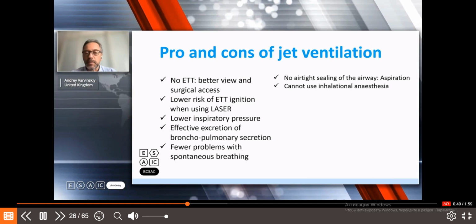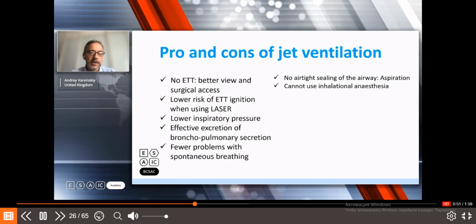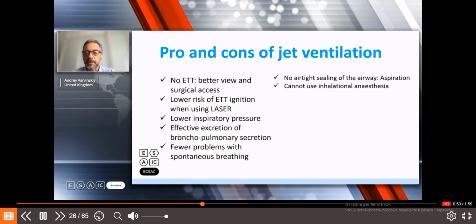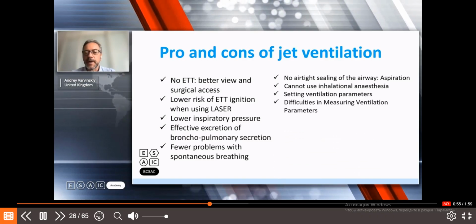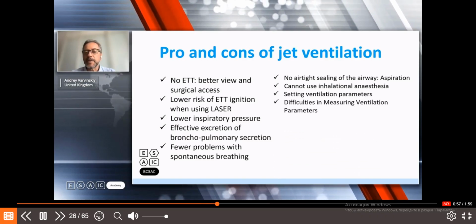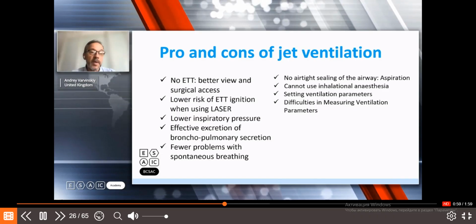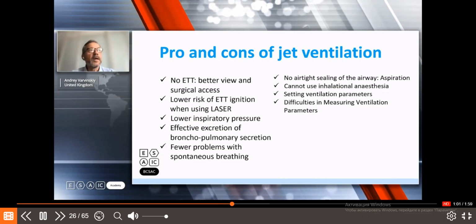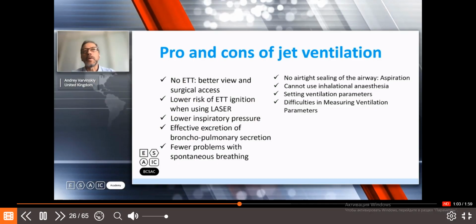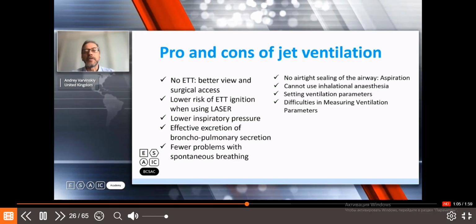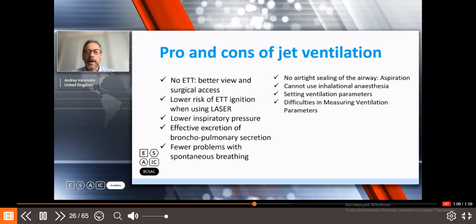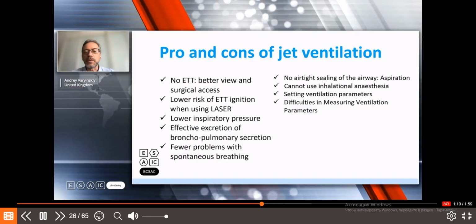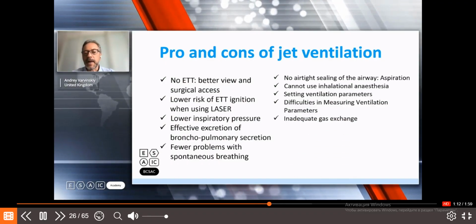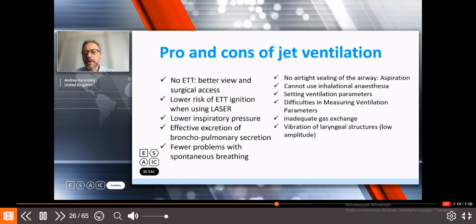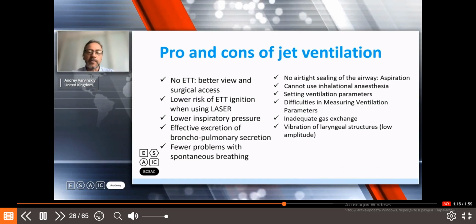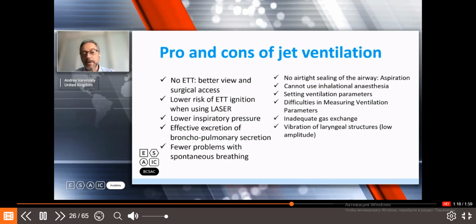You cannot use it with inhalational anesthesia, so the only technique you will be using with jet ventilation is obviously total intravenous anesthesia. Setting parameters could be difficult to measure, so it's more difficult to assess how much you deliver in terms of tidal volume, minute volume, and what your CO2 elimination is. It could be inadequate gas exchange, and there could be a vibration of laryngeal structures, particularly at low amplitude.